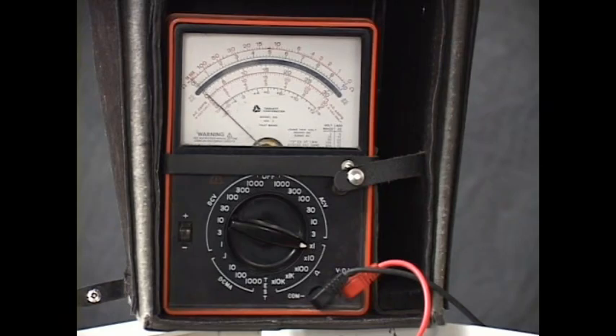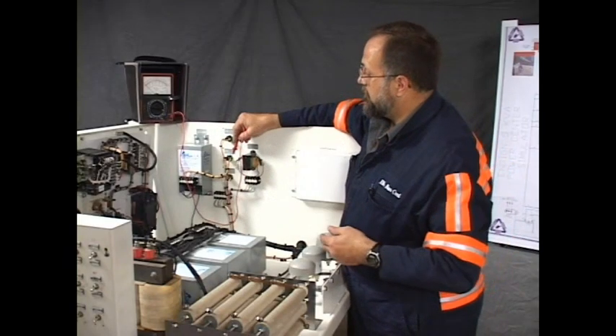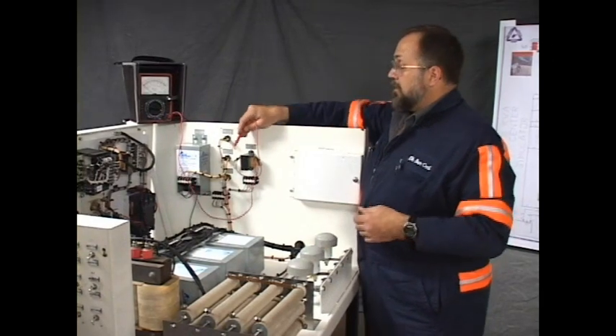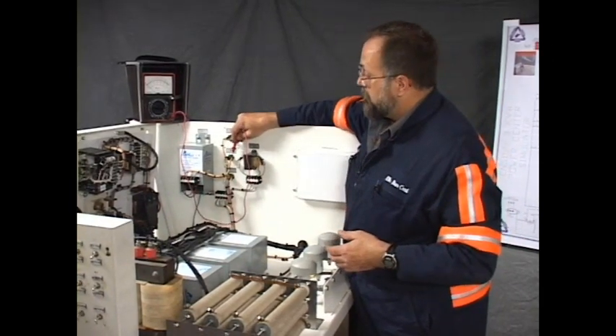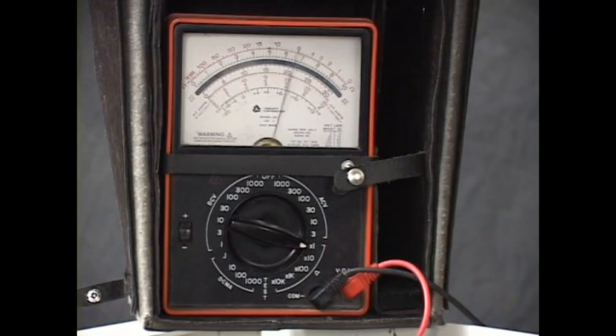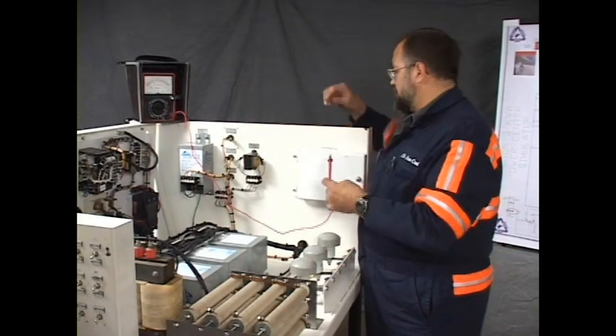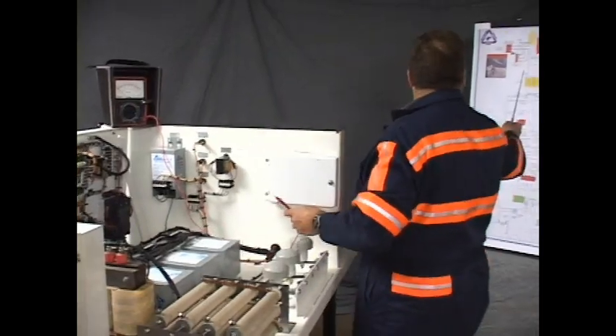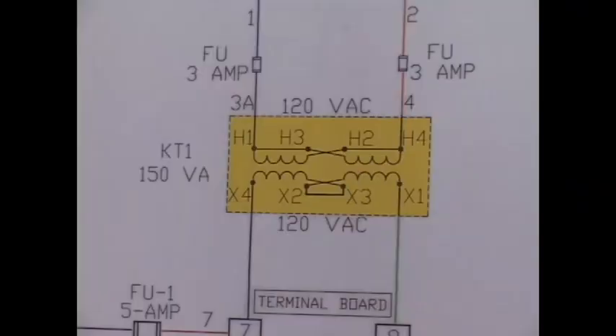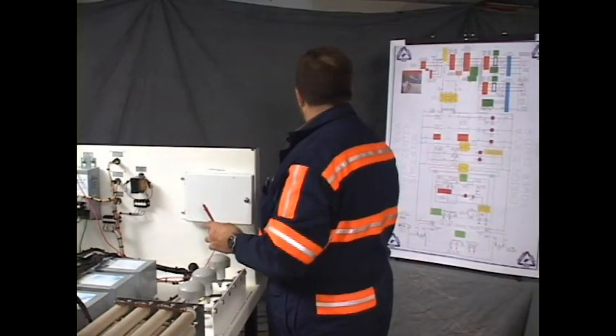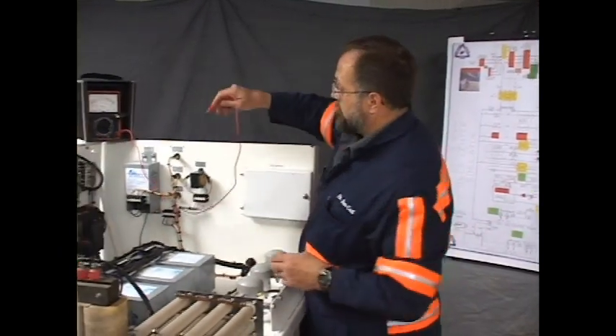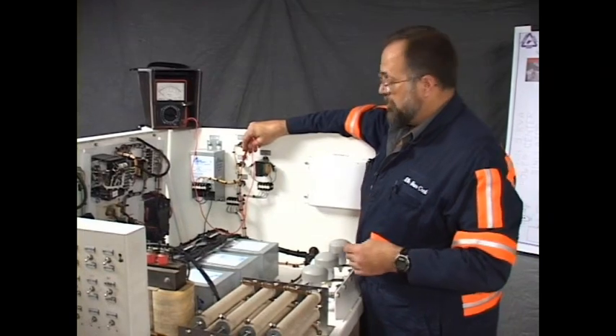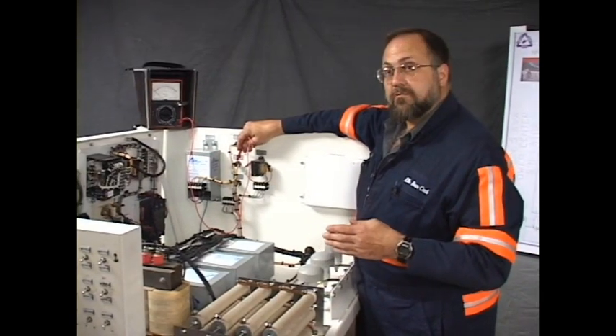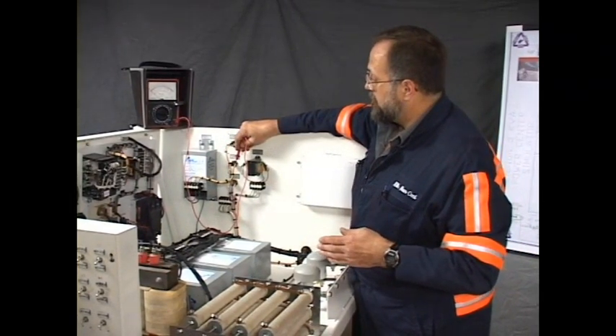That's as it should be. This wire is indeed intact. Now, I'm going to read through the fuse to the other probe, right there, and again, it reads no resistance, which is as it should be. I first read to the line side of the fuse, and then I moved to the load side of the fuse. That's as it should be. The fuse is intact. I have no resistance to the flow of current through the fuse.